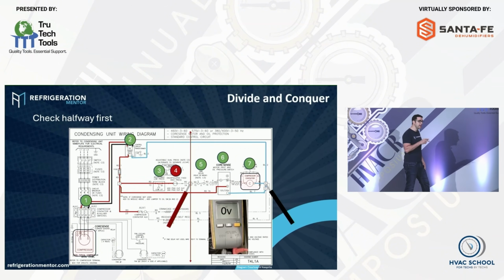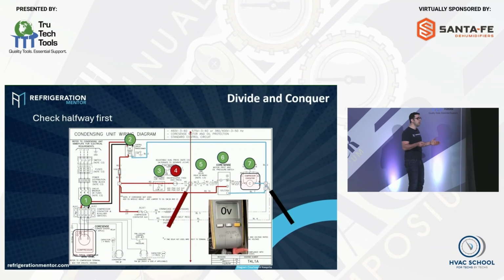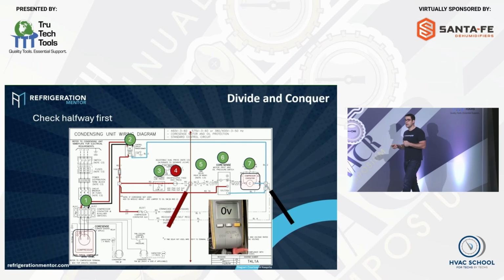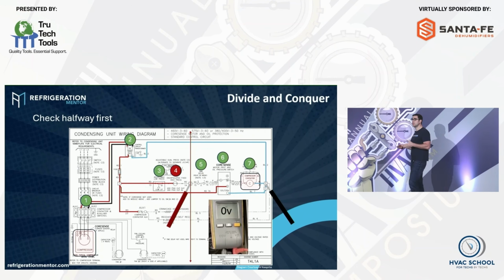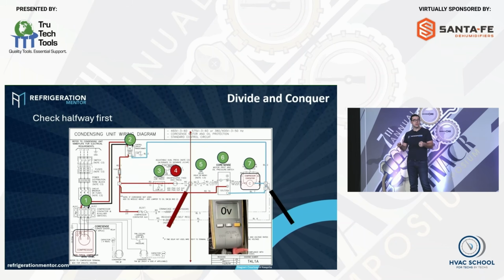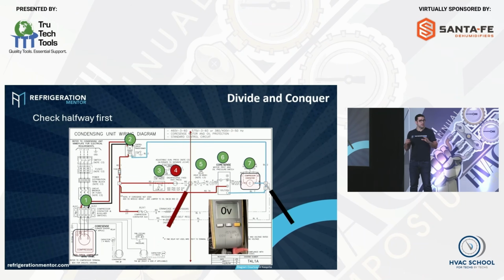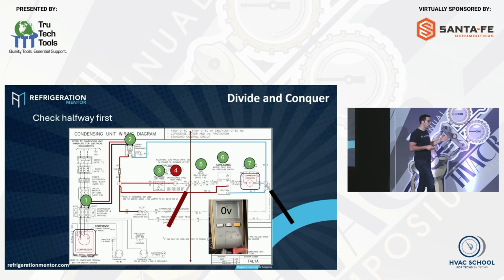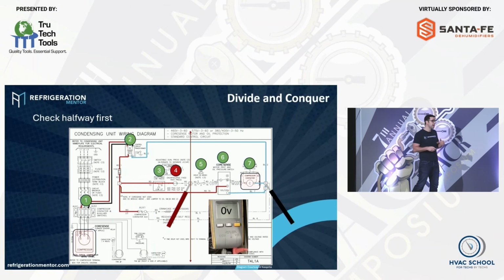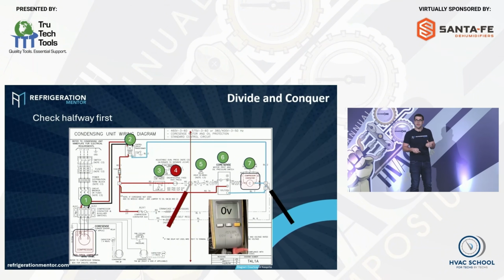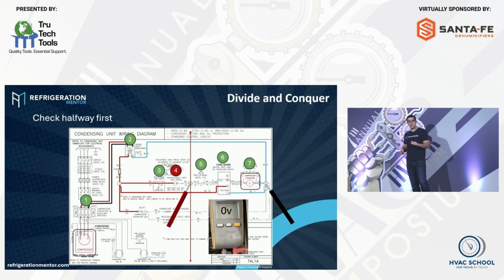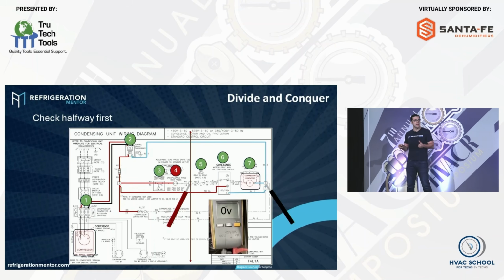So divide and conquer. How do we do that? Well, we use our meter effectively. In this example on this control circuit, we go from common to the middle. Use your terminal blocks. You do not have to be pulling everything off. All the manufacturers today have terminal blocks on it. It's a lot easier to troubleshoot today than older systems. And I understand there are a lot of systems that have all black wires and nothing is labeled and they've been butchered over the years. Totally understand. But the newer systems are really quick to troubleshoot.